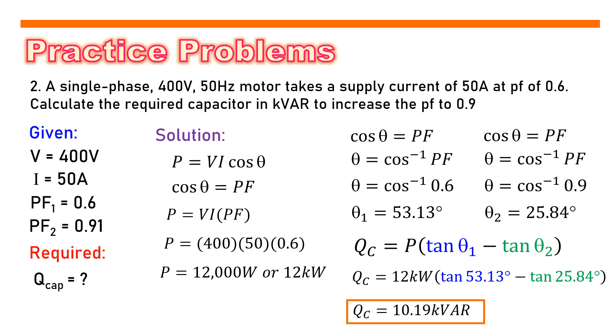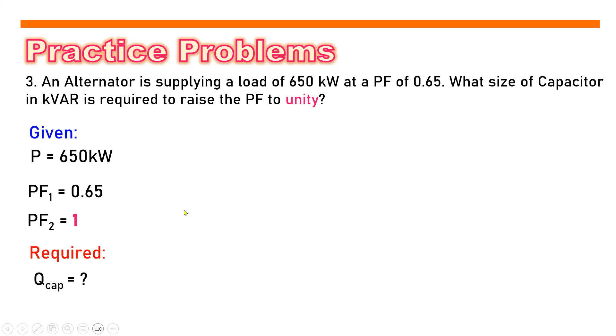Problem number 3: an alternator is supplying a load of 650 kilowatts at a power factor of 0.65. What size of capacitor in kVAR is required to raise the power factor to unity? Meron tayong mga given - power is already given, 650 kilowatts. Yung mababang power factor ay 0.65, at desired power factor natin, power factor 2, is equals to 1. Kaya kailangan nating solve for the size of the capacitor bank in kVAR.